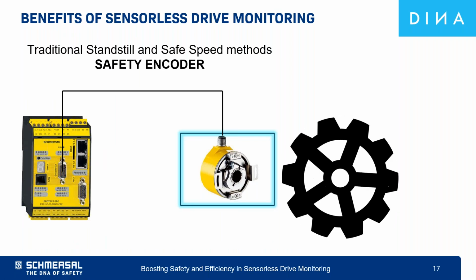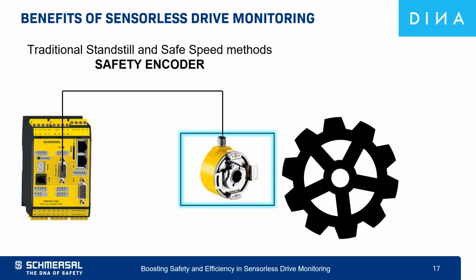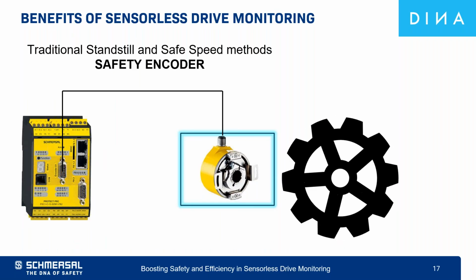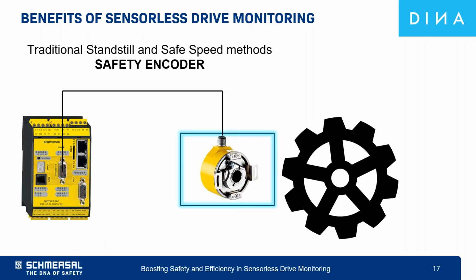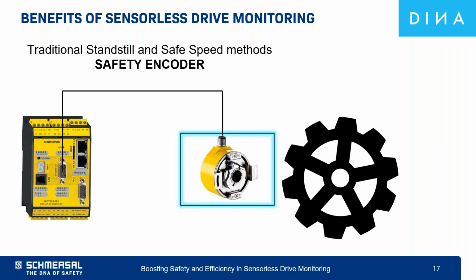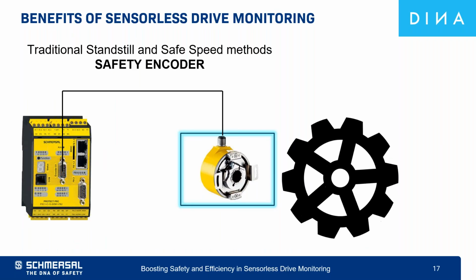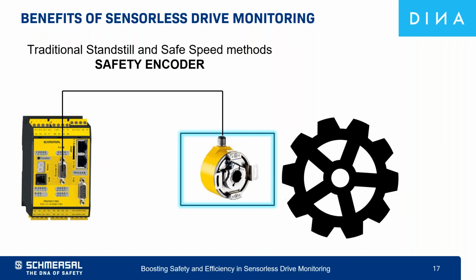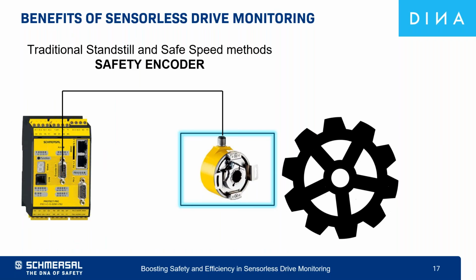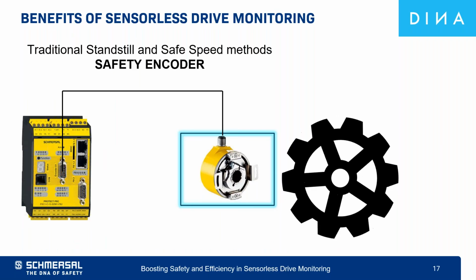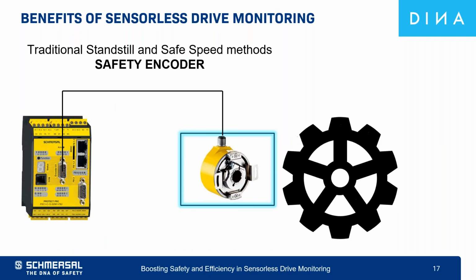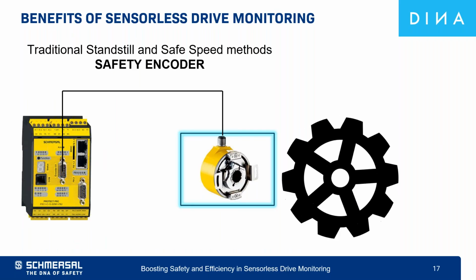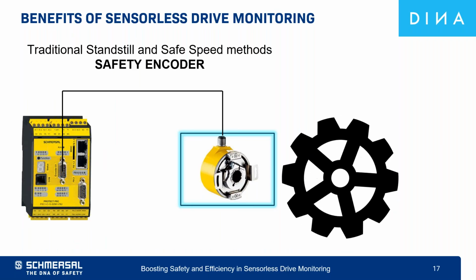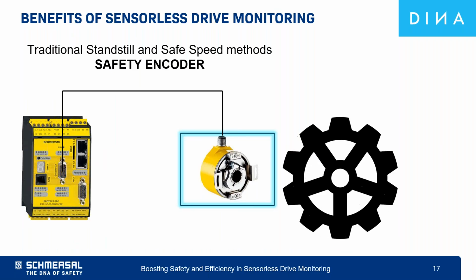They are an electromechanical device, and just like any electromechanical device, they'll wear out over time. In most cases, that 20 years or 1 billion revolutions can be, just as an example, if you were running 500 RPM, 24 hours per day, 365 days per year, that would actually only leave you with a life expectancy of about 4 years. That's just as an example. So this kind of thing should be calculated and considered so that you're making the right choice for this solution.